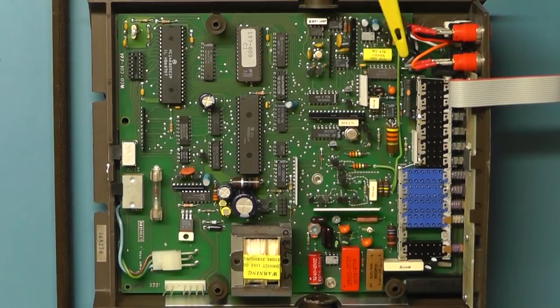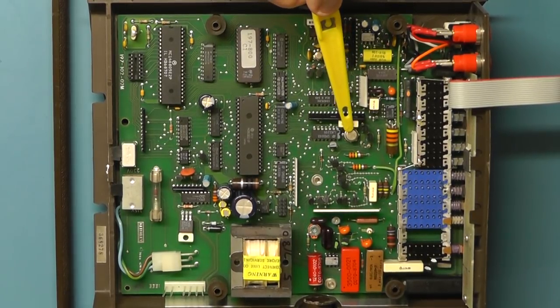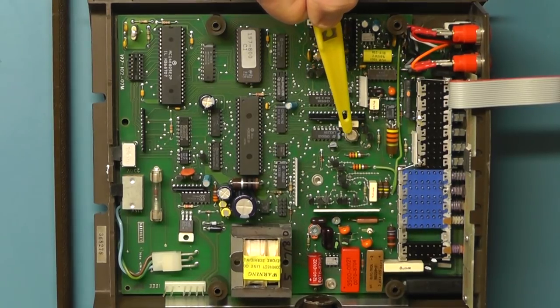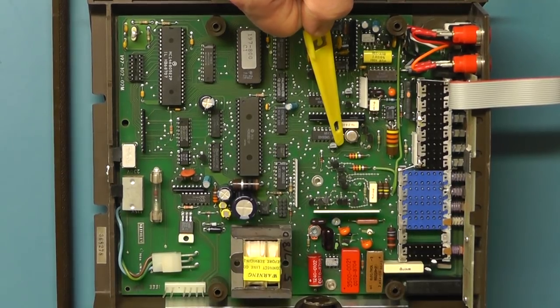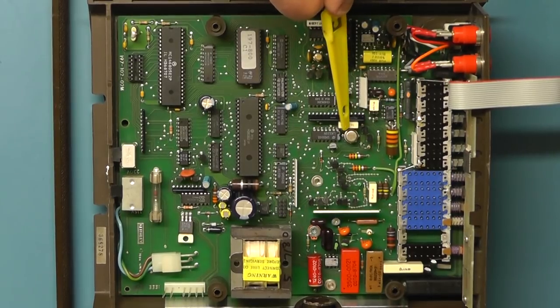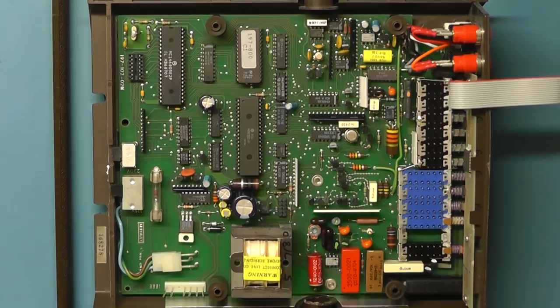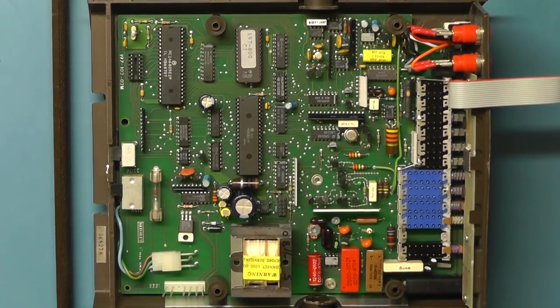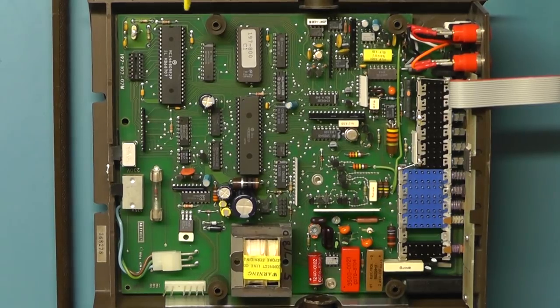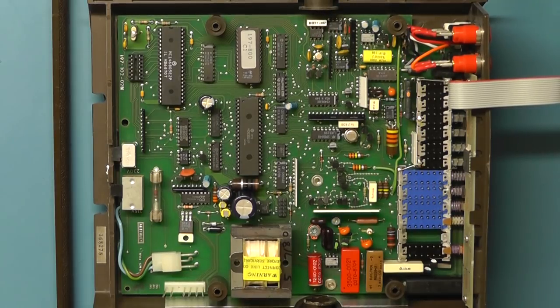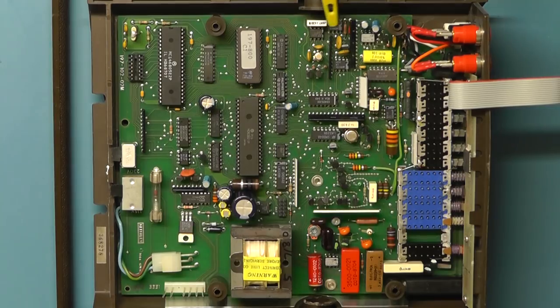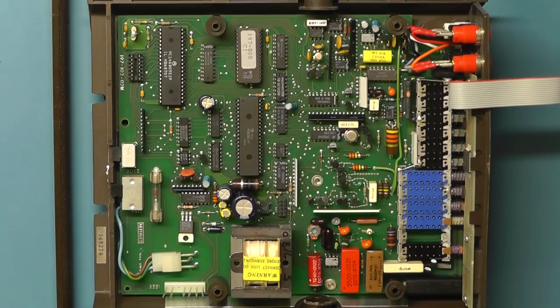One other difference I've noticed here is that the operational amplifier there that's been used on the input circuitry this particular one is a AD542 it's a very high-performance input buffer amplifier so that's a better quality than what we saw on the model 175 so I think in general terms the circuit and the layout is very similar to the 175 model but they're using slightly better specified components and the tolerance on the voltage reference Zener is much better and together with the five and a half digit display they have that's how they get the improved accuracy.